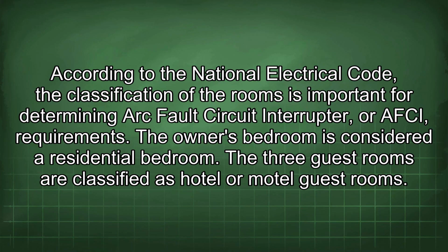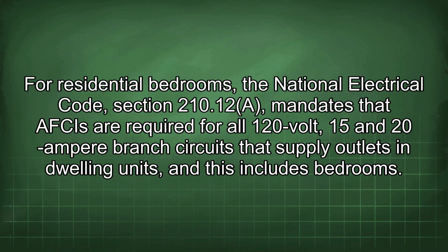According to the National Electrical Code, the classification of the rooms is important for determining arc fault circuit interrupter, or AFCI, requirements. The owner's bedroom is considered a residential bedroom. The 3 guest rooms are classified as hotel or motel guest rooms. For residential bedrooms, the National Electrical Code, Section 210.12(A), mandates that AFCIs are required for all 120-volt, 15 and 20 ampere branch circuits that supply outlets in dwelling units, and this includes bedrooms.